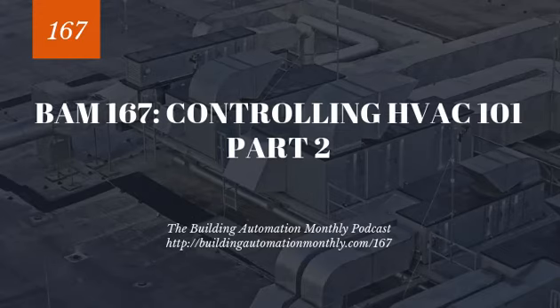Now, with constant air volume, we don't have that capability to have variable air volume based on the space temperature. So what we do is we'll have a constant volume and we'll look at the average space temp and reset the discharge air or the supply air, depending on what you want to call it. But most of the time it's called discharge air. And we'll reset the discharge air set point, typically between 55 to 65 degrees. That's because we are not varying the air volume within the space.